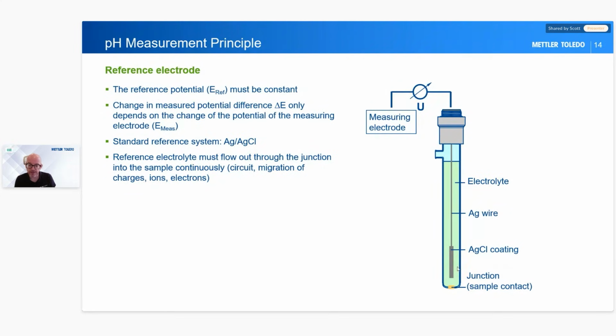What we want from this reference electrode is for the electrolyte in here to flow out into our sample. When this electrolyte flows and the ions flow out of here into our sample, it pulls ions off this silver chloride coating and generates a reading. The most important things here are that the electrolyte inside is clean, constant and always the same, and that this junction at the bottom is open, clear and usable.